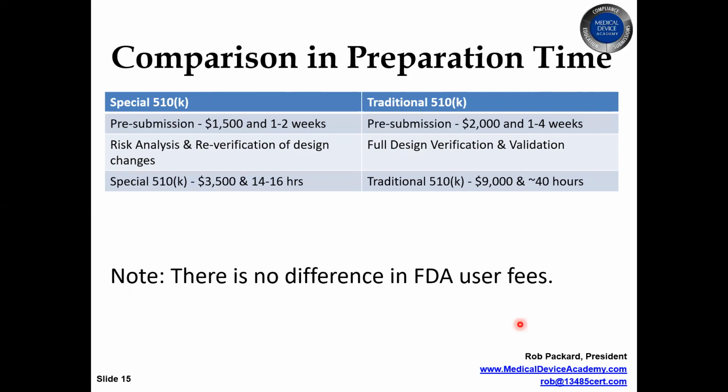So risk analysis is typically only required in a 510K under 2 circumstances. Number 1, it says so in a special controls guidance document: please identify the following risk controls that you've implemented or how you've addressed the following risks. So that's one common phrase that you'll see in a special controls guidance. The other scenario when you need risk analysis is when you have software. So if you have a software product, they require risk analysis for the software portion of the device.